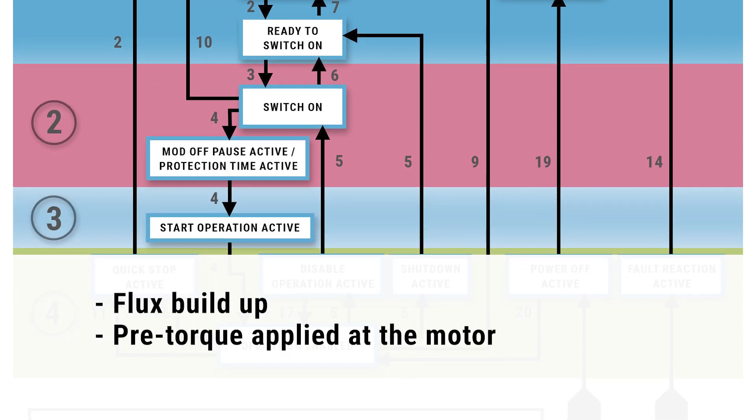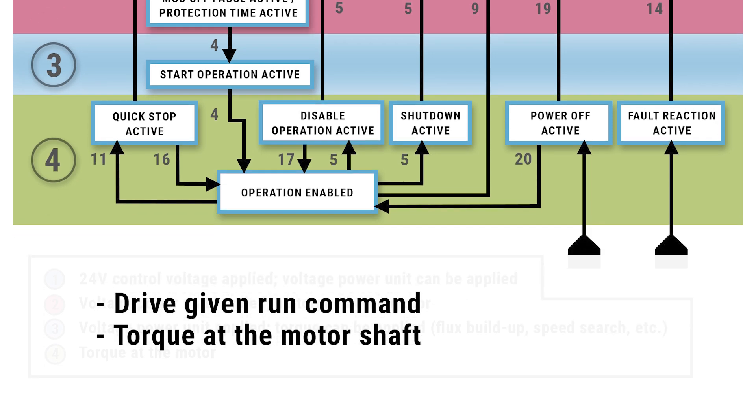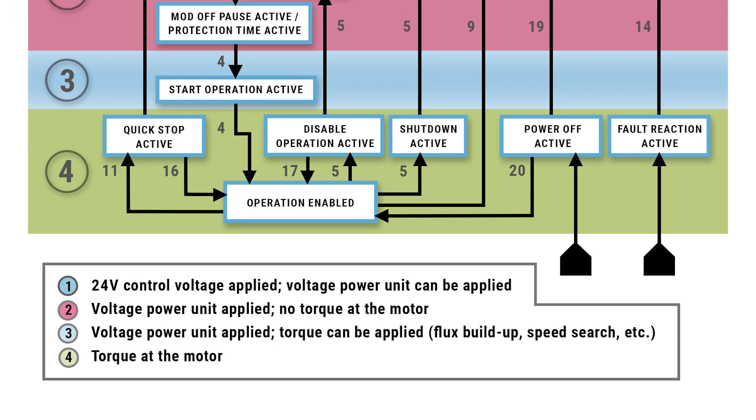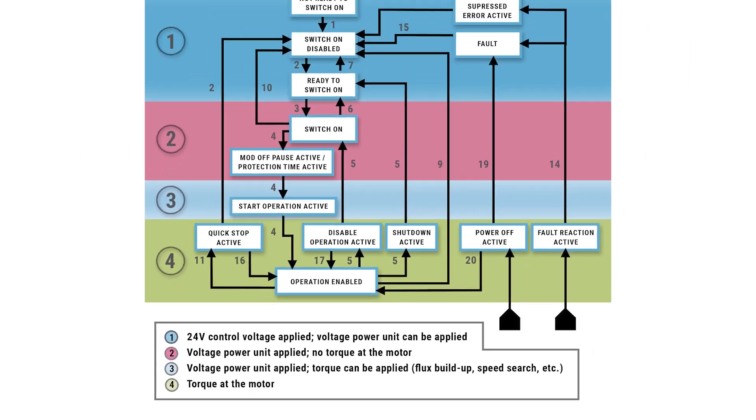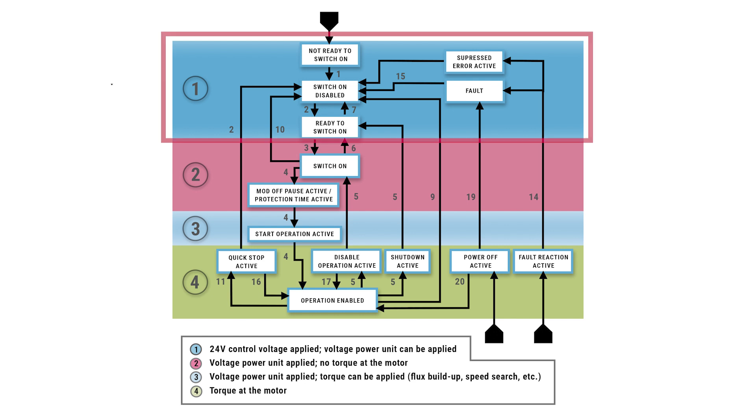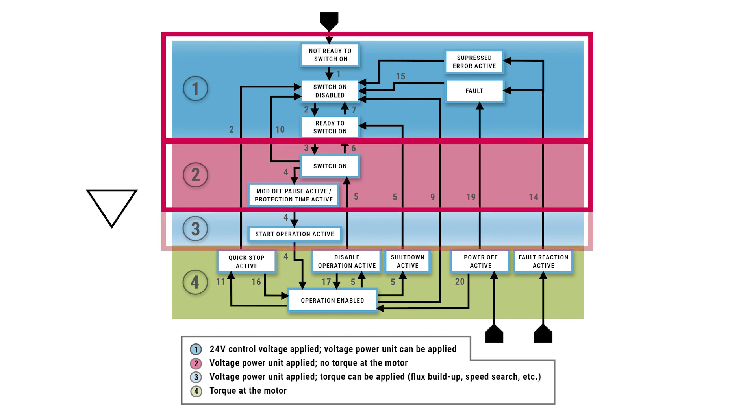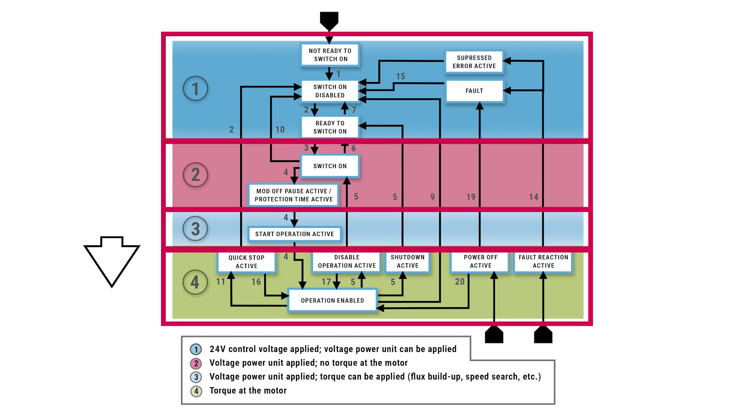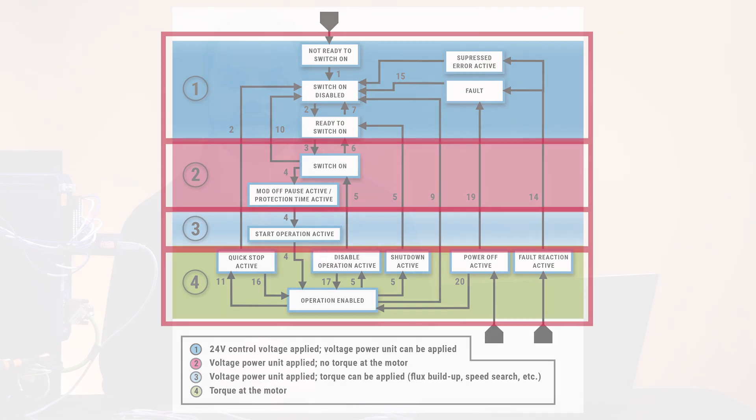Section three is where flux buildup happens and pre-torque can be applied, given section two has been reached. Section four is where the drive is given the run command and there is torque at the motor shaft, given that all previous sections have been reached. It's important to note that the device must logically progress through this series of states until it reaches the operation enabled state.